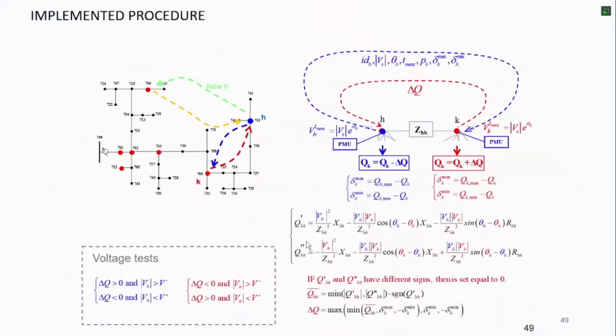PMUs are time synchronized, GPS-based time synchronized. Yes, the phasor measurement units need synchronization in order to estimate the angle, because they need the pulse that is also given by the GPS each second. It is the reference for the shift of the waveform of the voltage with respect to zero time, and that gives the angle of the voltage. The angle is the angular delay between the peak of the voltage and the zero reference of the time. Is that good?